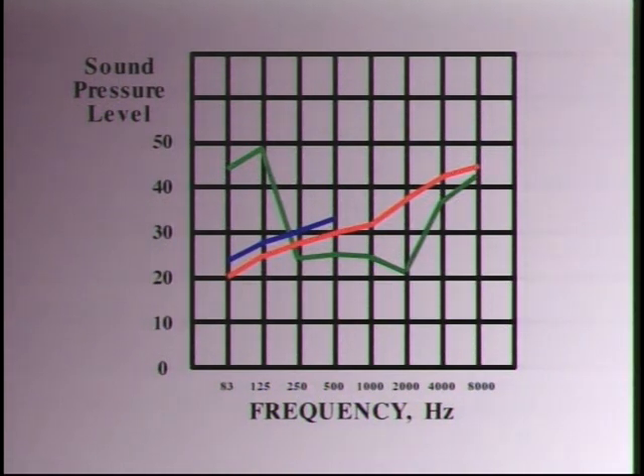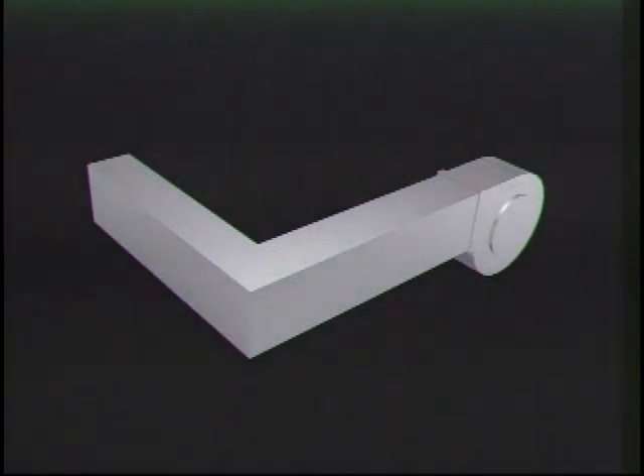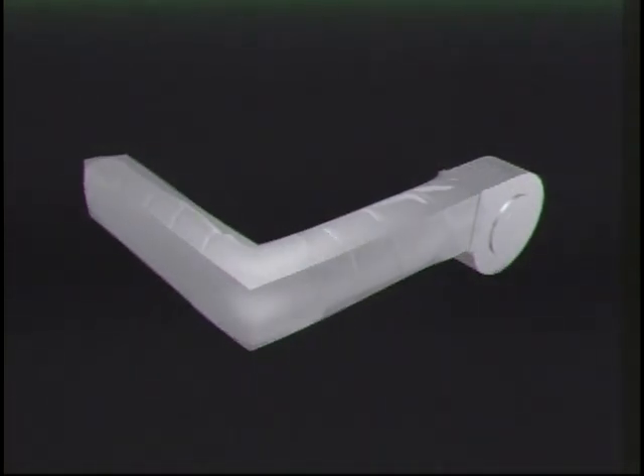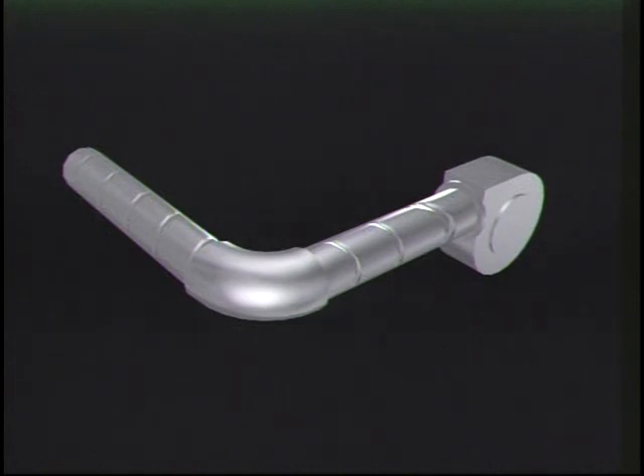extremely important and useful. For example, one would hear a 125 Hz frequency fan noise of 100 decibels breaking out of a rectangular duct at about 77 decibels, or 61 decibels above the human hearing threshold, which is moderately loud noise. The 100 decibel fan noise at 125 Hz would break out of a round spiral duct at about 50 decibels, or 34 decibels above the hearing threshold, a quiet sound level where one should hear whispered conversation 6 feet away.